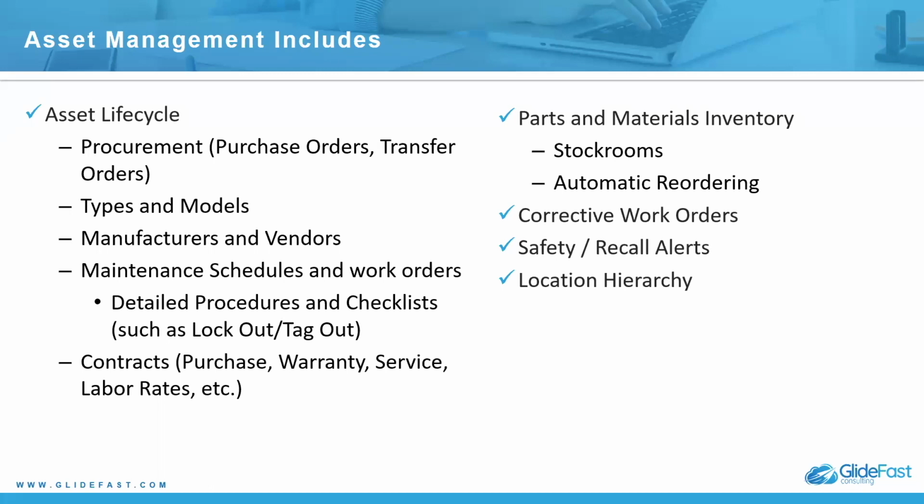You can also have detailed procedures and checklists. So imagine a facilities technician being sent out to do an annual cleaning on some furnace, an HVAC component. And one of the things that they have to do before they can even start their annual maintenance is a lockout, tagout procedure. And so that's what those checklists are for. You have a pre-checklist as well as a working checklist, and that can help remind them of specific steps they need to take.